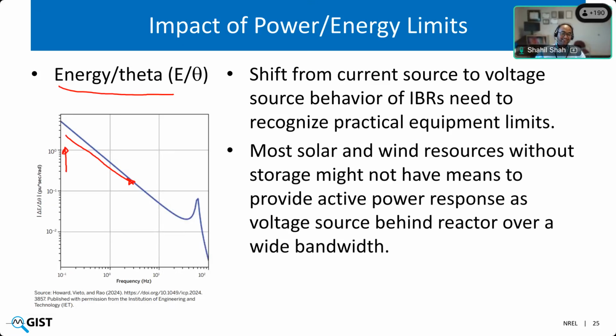So what it means is that to keep that P by theta gain really flat, as you go towards lower and lower frequencies, you would need more and more energy response or energy storage within the device to meet that requirement. And again, which might not be possible for certain resources which do not have inherent storage inside them. So when we apply this performance metrics, we have to be mindful about which technology we are applying it to, whether something with energy storage like eStatCom or battery energy storage system, or something without internal storage.